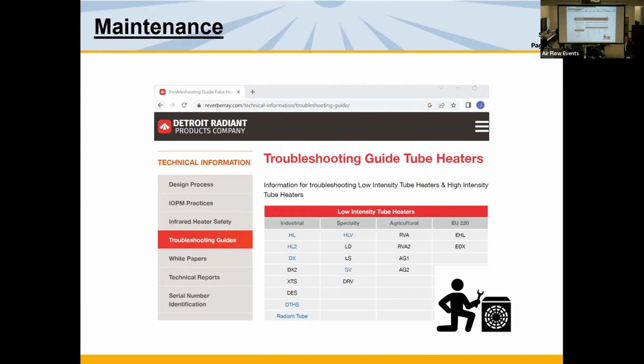But if the heat exchanger gets all full of crud, it starts harnessing the energy and eventually the heat exchanger can fail. So once a year, we try and put a lot of tools out there: videos on YouTube, all of our manuals, troubleshooting guides. We're really good about answering the phone. We encourage people, once a year, to go look at the heater, typically in the startup season, and make sure that the basics are there.